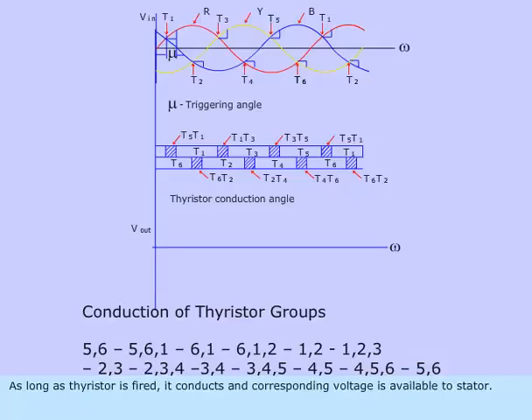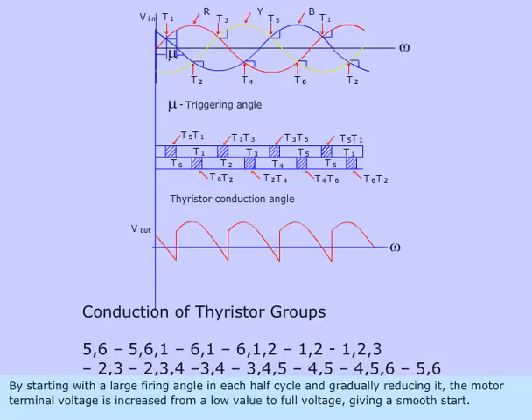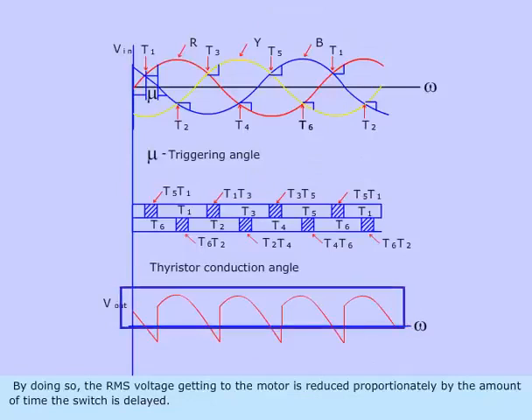As long as thyristor is fired, it conducts and corresponding voltage is available to stator. By starting with a large firing angle in each half-cycle and gradually reducing it, the motor terminal voltage is increased from a low value to full voltage, giving a smooth start. By doing so, the RMS voltage getting to the motor is reduced proportionately by the amount of time the switch is delayed.